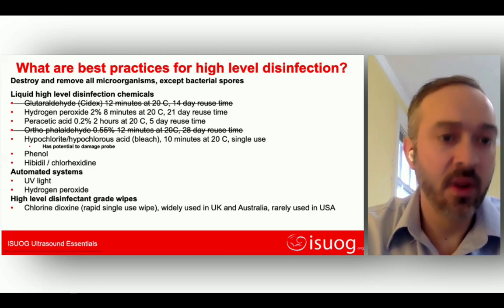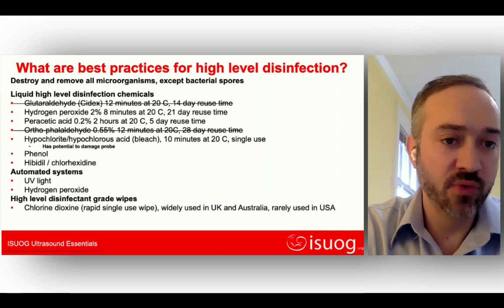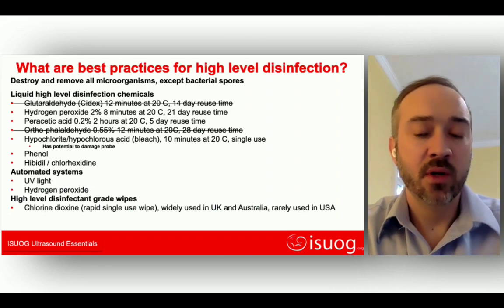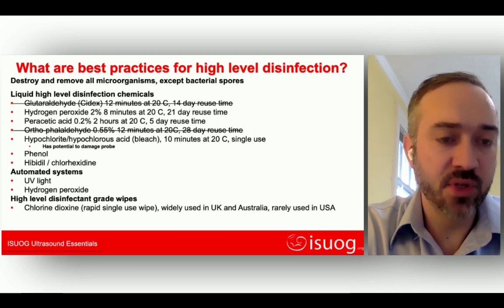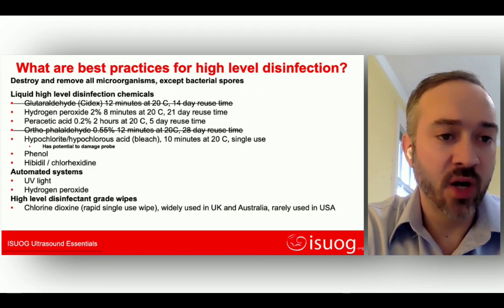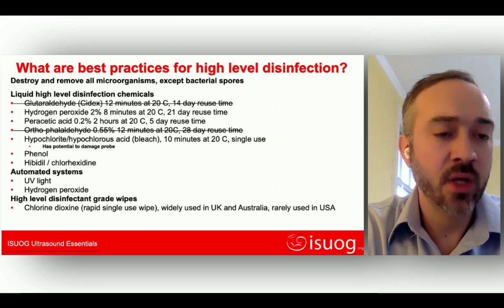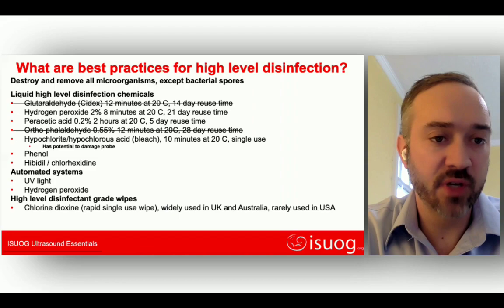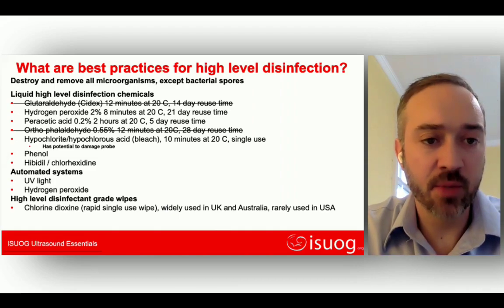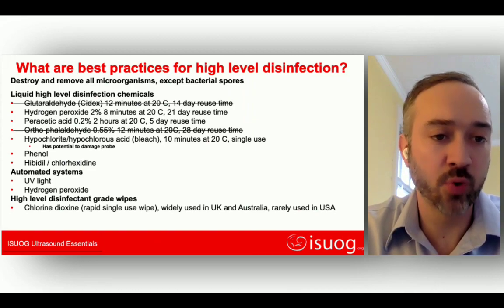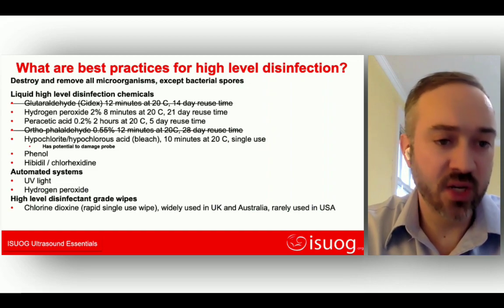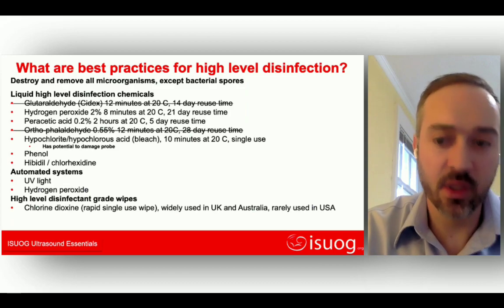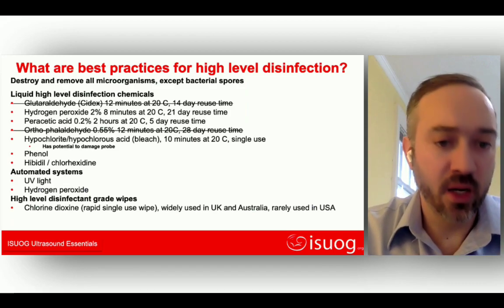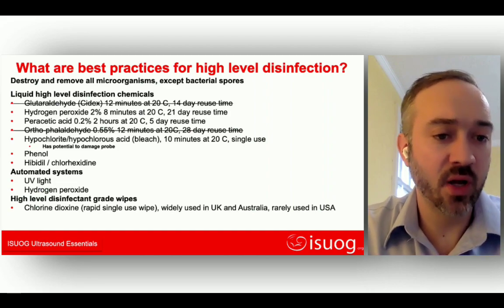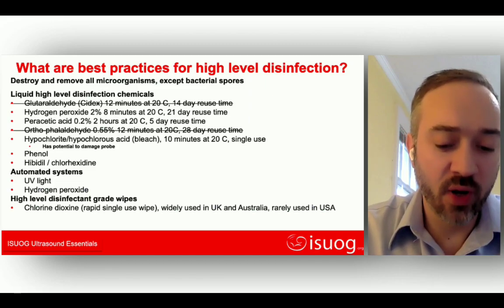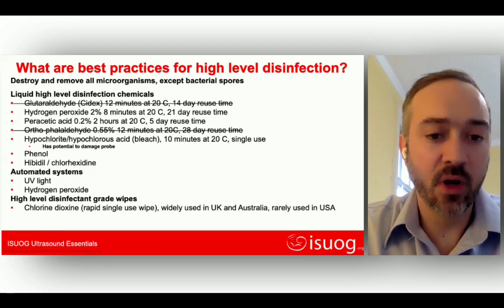In terms of high-level disinfection, this gets a little more complicated because this destroys and removes nearly all microorganisms except bacterial spores. There are a number of different products and systems and ways to do this. Some of the common ways and common chemicals are listed here, but basically this is divided into 3 different ways of disinfection. One involves a high-level disinfection chemical with a soak and a soak time, and then allowing the probe to dry and then reusing it. The second is an automated system that uses chemicals or UV light. I believe Angela uses one of these in her unit. And in some areas of the world, there are high-level disinfectant grade wipes, such as chlorine dioxide. These are widely used in the UK and Europe, but are not approved in the US.